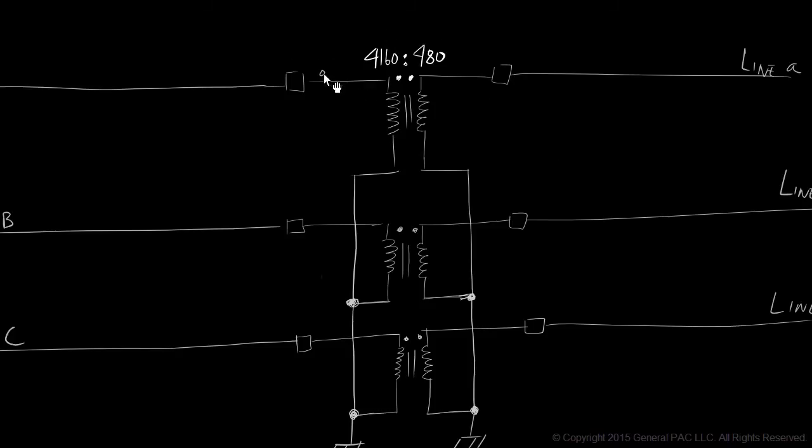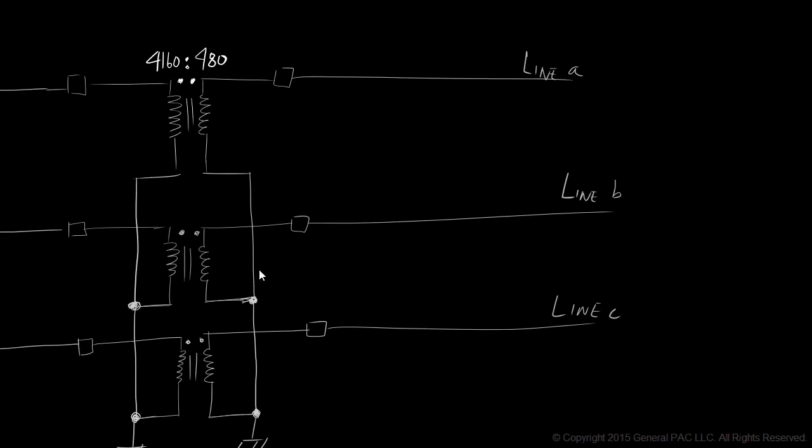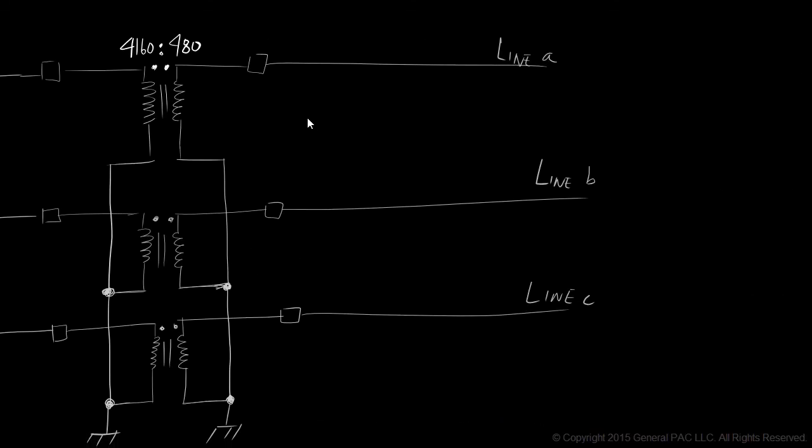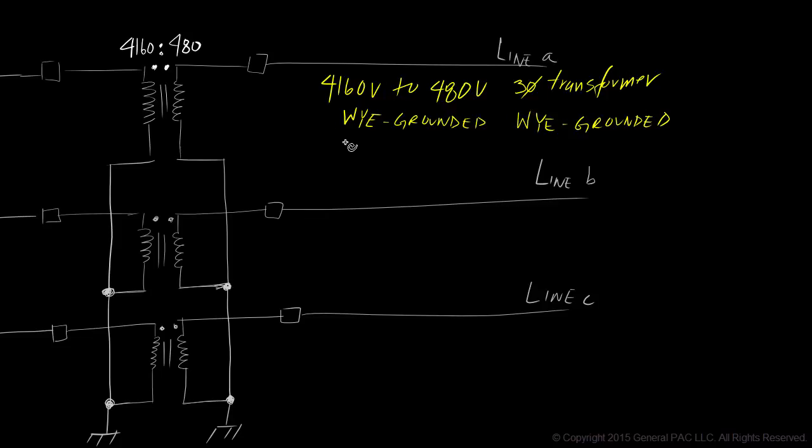This, my friends, is our YY-connected three-phase transformer. And if we were to describe this particular transformer connection to someone, we'd say that we have a 4160 to 480 volt three-phase transformer. It has a Y-grounded-Y-grounded connection. Both the primary side and the secondary side is solidly grounded with no neutral impedance.